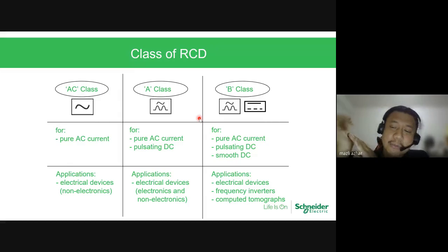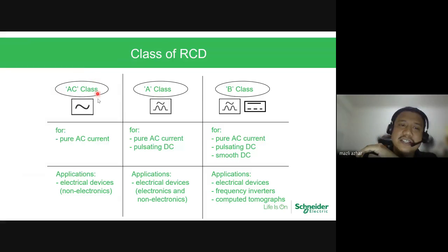Okay. So normally in standard installation nowadays, they still use AC class. So what will happen when you use AC? Let's say there is a leakage after the converter. What will happen? It will not detect and you still get electrocuted. So it's very important nowadays for me, even my manufacturer, to educate the consultant, to educate the people. You need to shift from AC to A class. Why? A lot of components, a lot of loads, a lot of equipment nowadays have a converter inside. So to ensure that you are still protected when a leakage occurs.